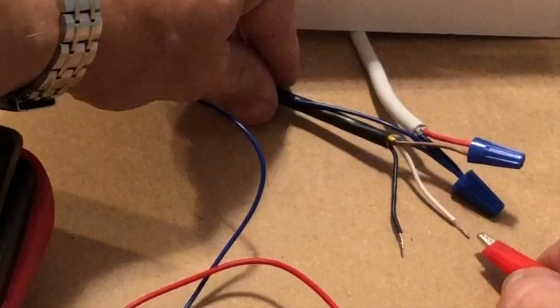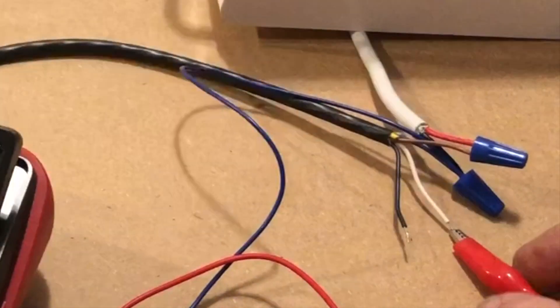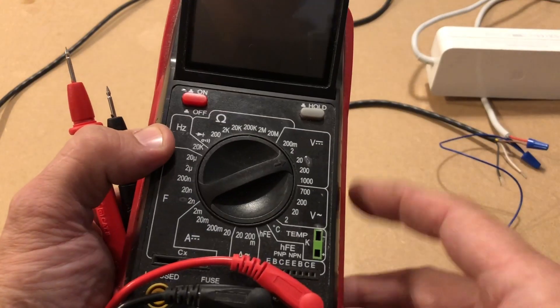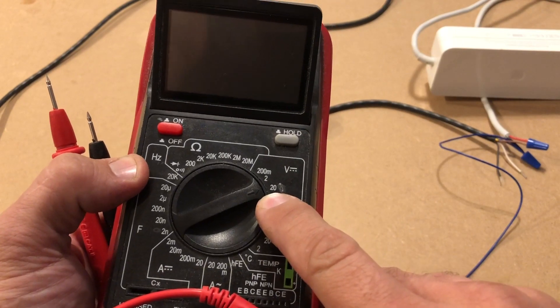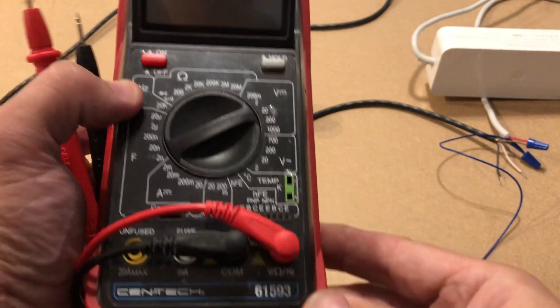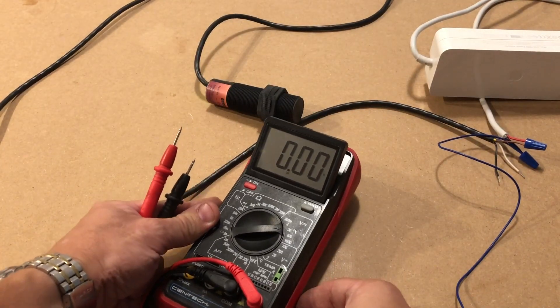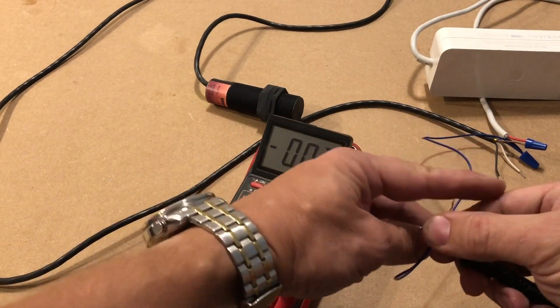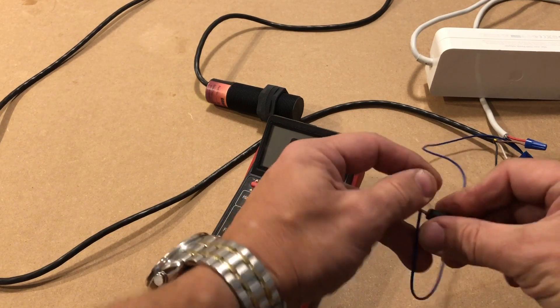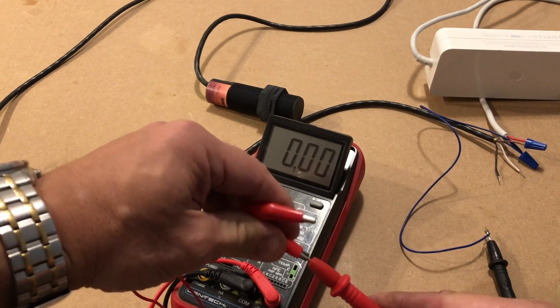First I am going to test the white wire which outputs 0 to 10 volt DC analog signal. Making sure that the proper range of the multimeter as well as probe clamps are selected, we connect the black probe to our common wire and the red probe to our signal wire.